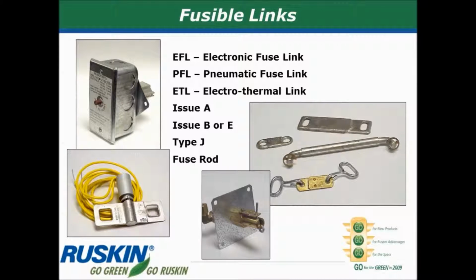The dampers actuate using fusible links. Sometimes that's just simply a couple of pieces of metal soldered together, and when it heats up, that solder melts and the two sections pull apart, which allows the curtain blade of the damper to close. With a combination fire smoke damper that's motor driven, there is no fusible link that melts. There is instead what's called an electronic fuse link, the EFL, and that's a little heat sensor. And when the temperature of that sensor goes up to the 165 or 212 degree limit, it will actually signal and shut off the power flow to the actuator, which allows the spring return to close the blades. There are a number of different sizes and shapes of these various items, depending upon what's needed for the particular application and the type of damper.